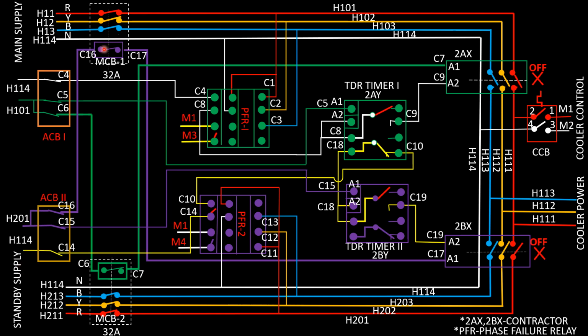Now suppose MCB1, MCB2, ACB1 and ACB2 are switched on. PFR1 gets power and makes these contacts. TDR timer 1 gets neutral connection at A2 after presetting time. This contact makes the circuit to power contactor 2AX by throwing neutral at A2.